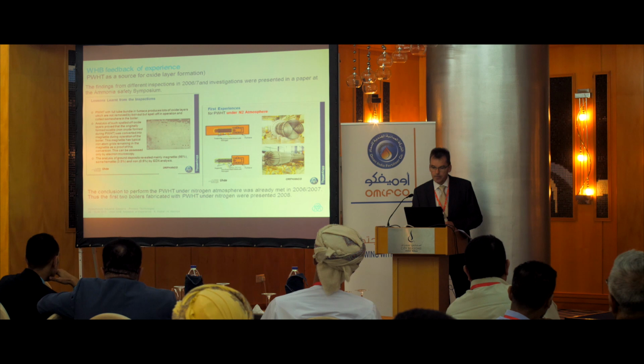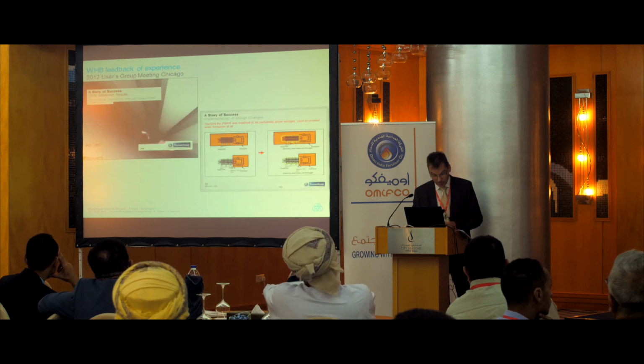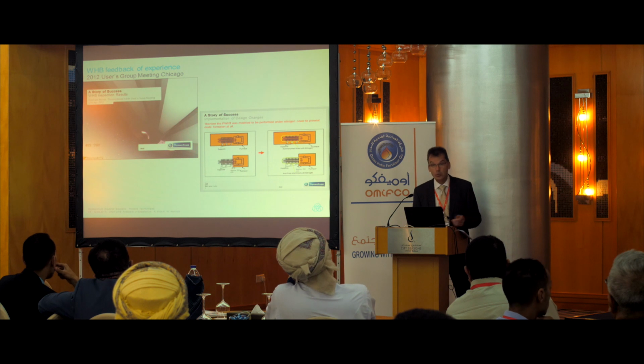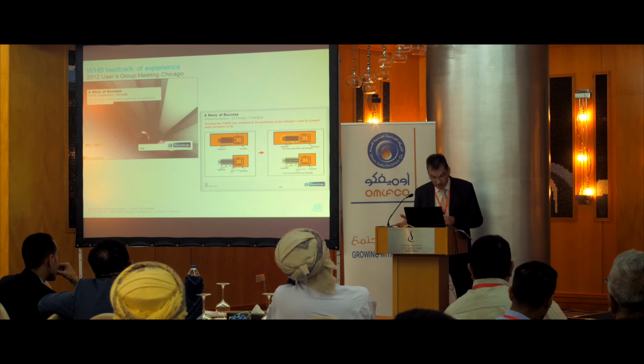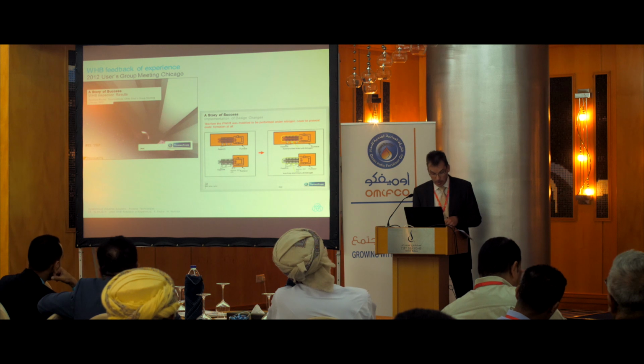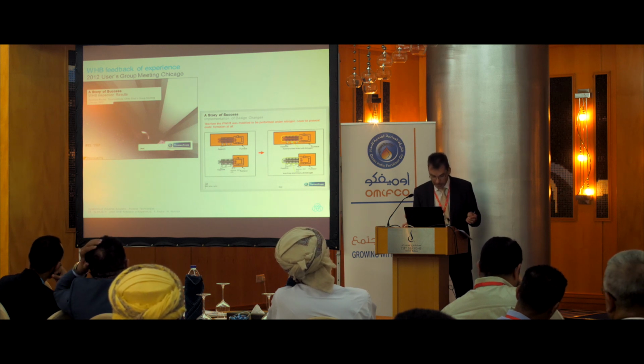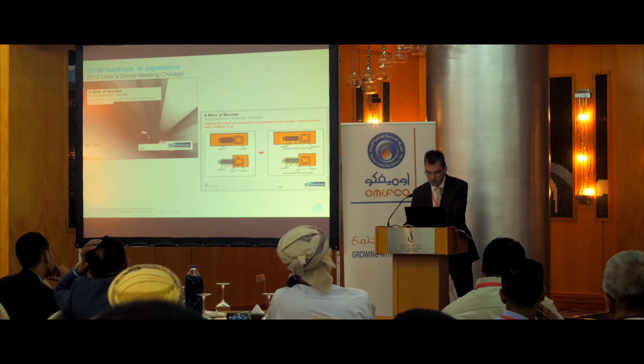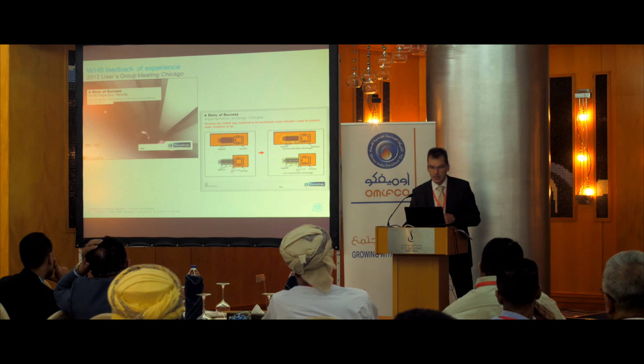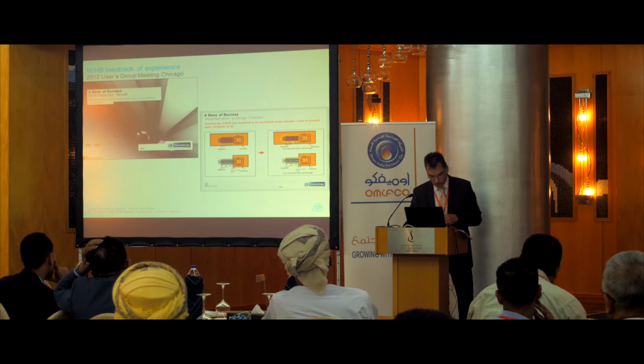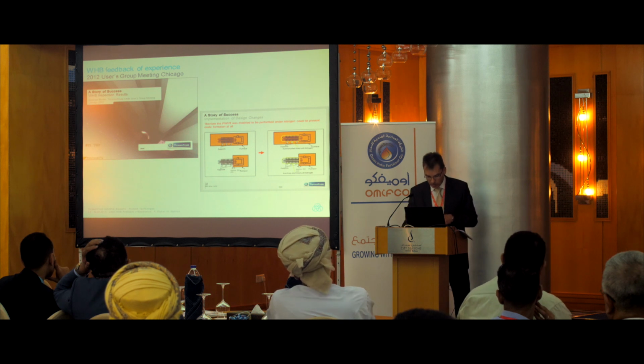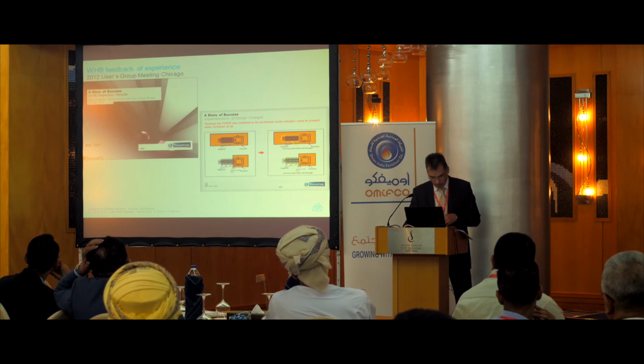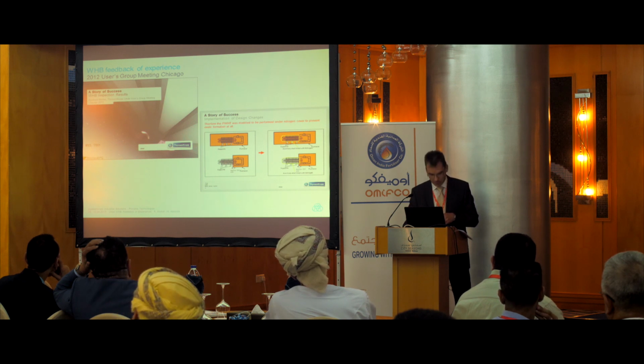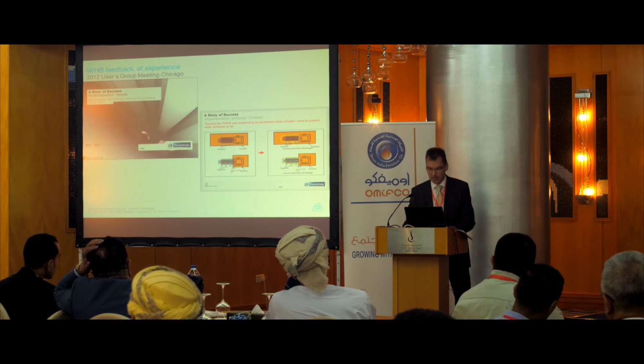So, was this now the story? Several borescope inspections of boilers in operation during 2008 and 2012 at different plants proved that the condition of the boiler on the shell side now was clean, free of spalled-off oxide layers and without deposition of magnetite on the tube surface. You see on the left side a typical picture with the borescope and the tube very clean and the wall clean. Consequently, our paper at the ammonia users meeting was titled A Story of Success. And now the corrosion problem in the boiler was solved. But it was too easy. You have been too pleased too early.